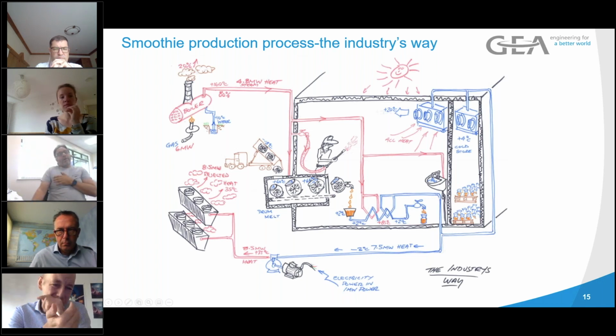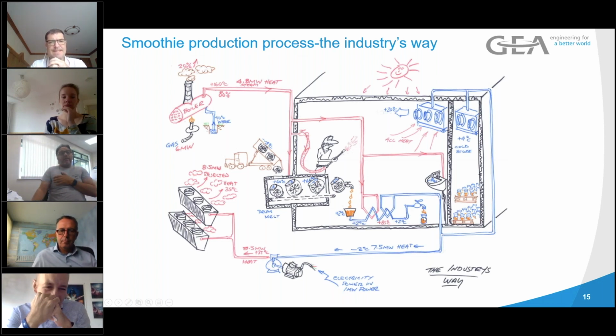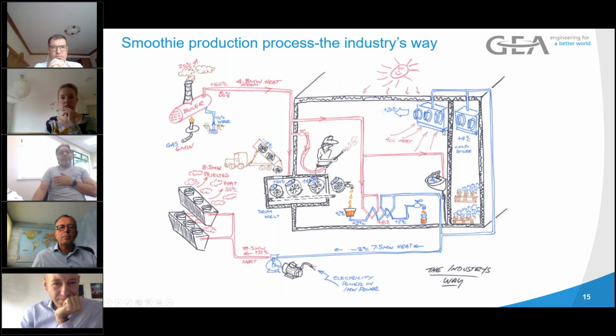Then you have the usual culprits running around spraying everywhere with hot water whilst you're trying to refrigerate the area. You have the pasteurization, and juice is normally pasteurized around 85 degrees, and the end product is 2. So it goes into storage at 2 to 4, and then it's distributed at that point. So explaining this in my sketch form, my comedic form, the heat's going in and we're removing it again here, and the refrigeration plant's rejecting 8.5 megawatt. Again, it's just not at the right temperature. So it's easy to boost that heat at 8.5 megawatts back up to a useful temperature.